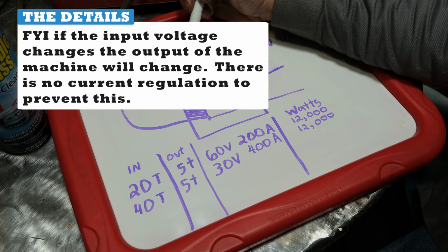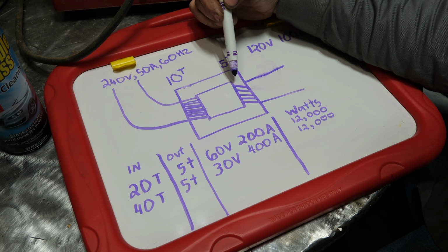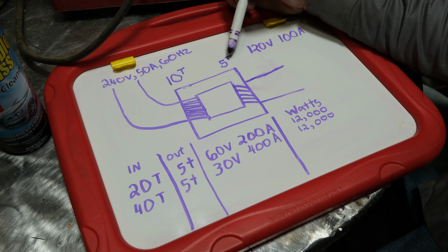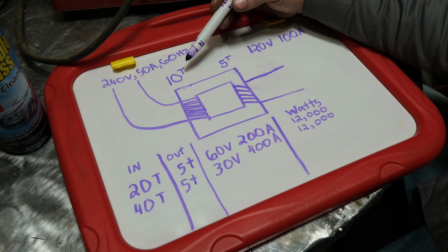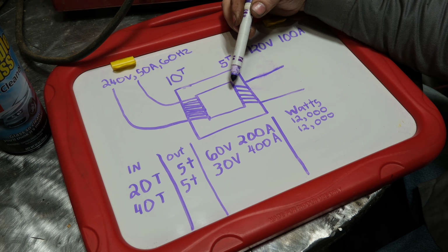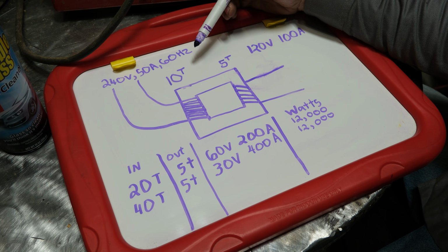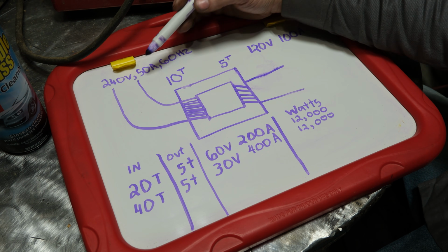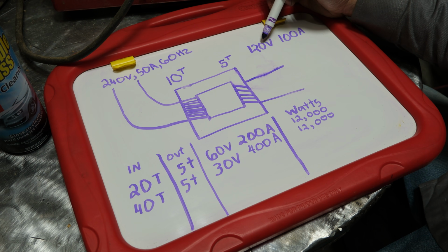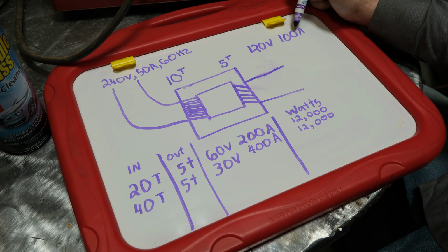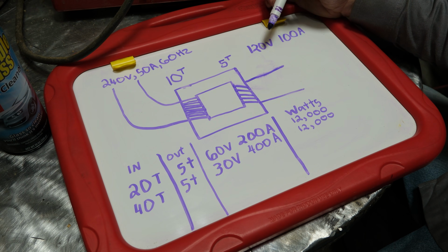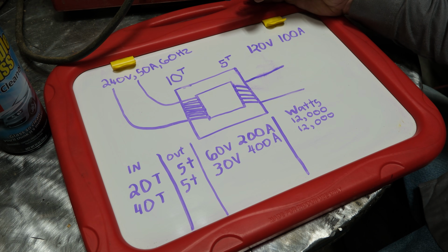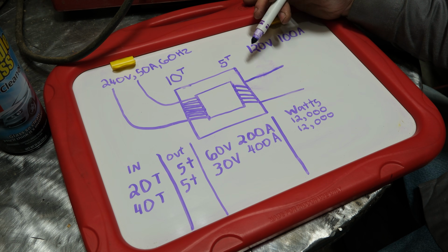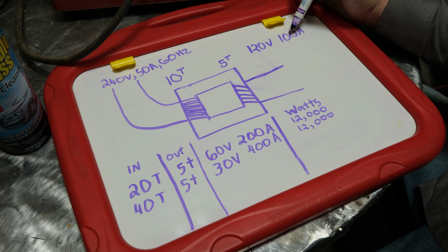And we have 10 turns or 10 wraps of wire on the input side of the transformer. On the output side, we have 5 turns or wraps of wire, and that effectively gives us a 10:5 ratio, which is going to reduce the voltage and give us more amperage. So we can more or less convert 240 volt 50 amp to 120 volt, half the voltage, at double the amperage. Now this is in a perfect world. As I mentioned before, these things are not perfectly efficient, nowhere near it. So our actual output and voltage is going to be less because of basically heat and other system losses. So in a perfect world, this is the conversion.